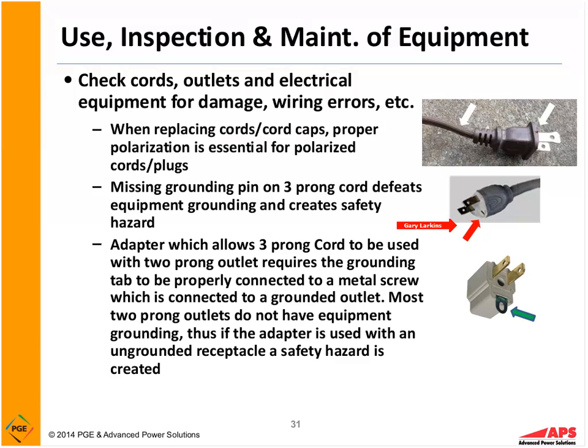Now here, this adapter is designed for that. You see the little green arrow there, where that tab is folded down and actually goes underneath the screw that holds a receptacle plate on, assuming there is a ground to the junction box that holds that receptacle. That's a big if, because many systems were not grounded. Many times people don't even bend that tab down. So how would I know? I would have to either call a qualified electrician, or I would have to hook this up and use a receptacle tester at the very minimum to make sure it's grounded. Otherwise, if I use one of those adapters here, I'm setting myself up for electrical shock.